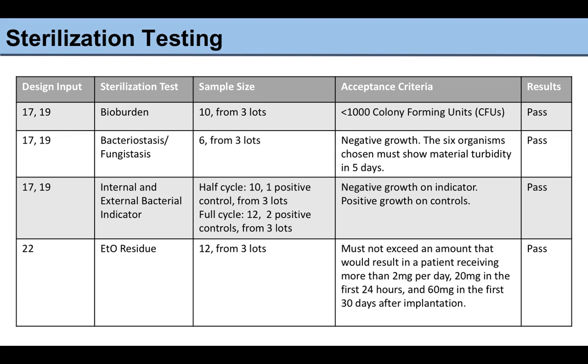We also tested the bacteriostasis and fungistasis with a sample size of 6 from 3 lots, and for this test to pass, it had to have negative growth, and additionally, the 6 organisms chosen for this test must show material turbidity in 5 days to confirm that the test was a good measure, which passed. We also tested the internal and external bacterial indicator. This test is also known as the half cycle and full cycle test. For the half cycle, we tested a sample size of 10 with 1 positive control from 3 lots, and for the full cycle, we tested an N of 12 with 2 positive controls, again from 3 production lots.